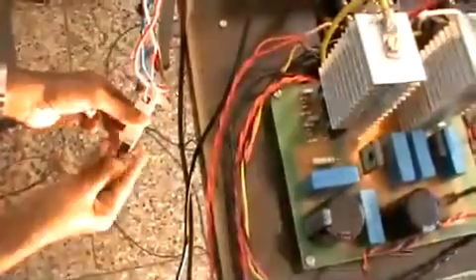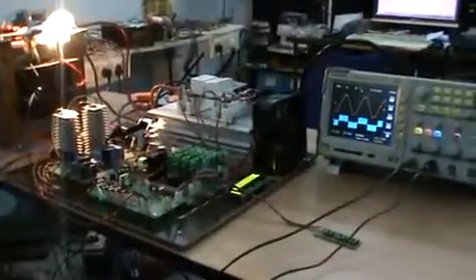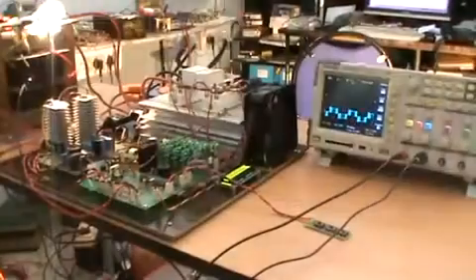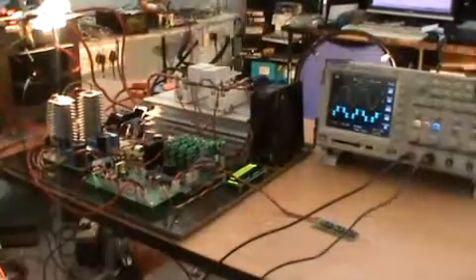The output is connected to 4000 watt halogen lamps, which will take a high surge at the starting, nearly 40,000 watt starting surge. Let us switch on the halogen lamp. You can see the battery current in the clamp meter. During surge load, cycle by cycle current limiting will protect the IGBTs.